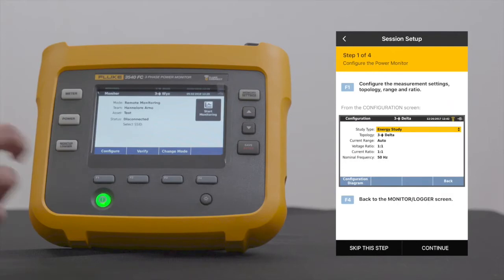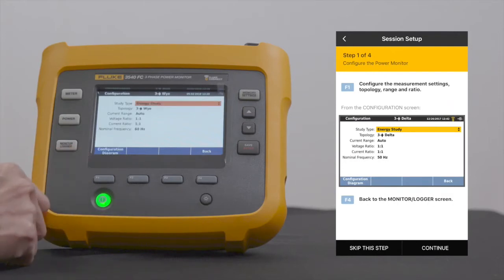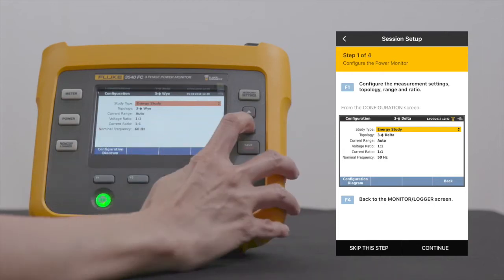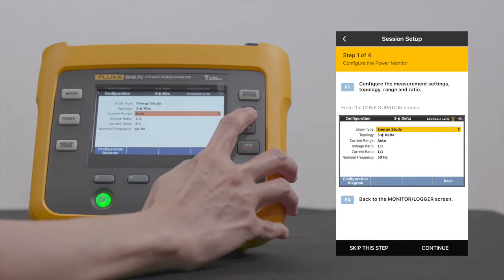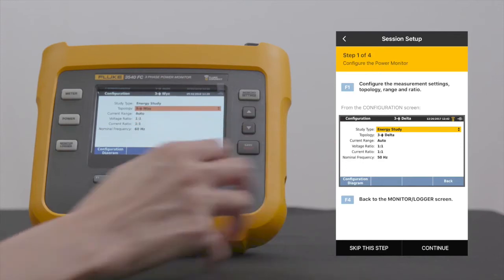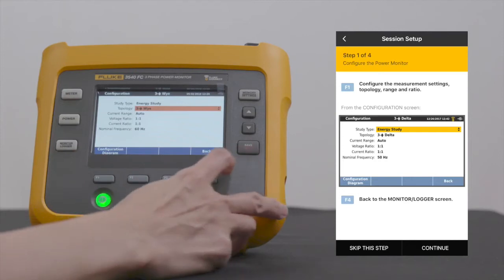On the Power Monitor, press F1 to configure the measurement settings, topology, range and ratio. Make your selections by using the arrow keys and the Save Enter button on the right side of the power monitor. When done with the configuration, press F4 to go back to the Monitor Logger screen.